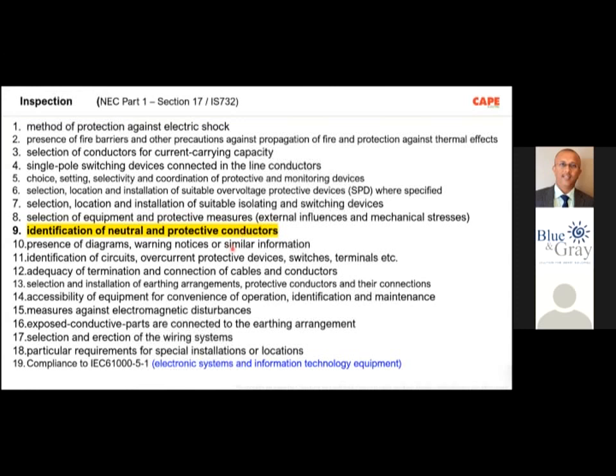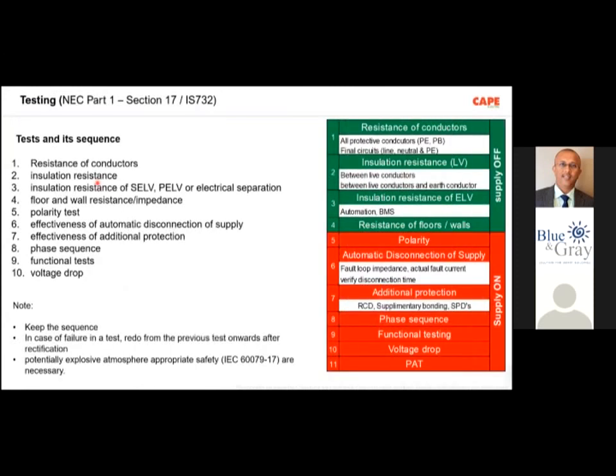Testing or inspection consists of 18 inspection points and 10 tests, starting with the resistance of conductors. Of course, in the standard you will see continuity of conductors. I changed it to resistance of conductors because people are misreading it. So resistance of conductors, insulation resistance, then the third is also insulation resistance. Number 6 is effectiveness of automatic disconnection of supply. And finally, the voltage drop.